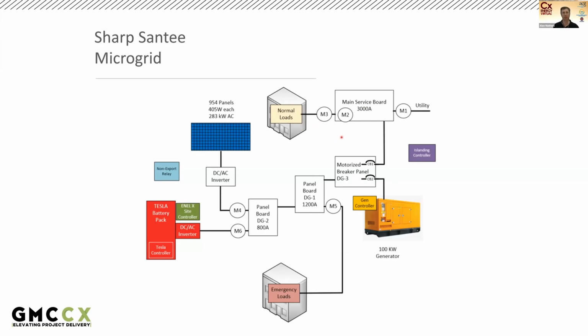And there are a number of power meters along with the system that I'm designating here as M1, M2, M3, M4, M5, M6. And I'll get into those in a little bit. But these power meters measure the flow and direction of power in the system. The system is paralleling, which means synchronous operation of multiple power sources connected on a common bus to provide power to the normal loads and emergency loads.